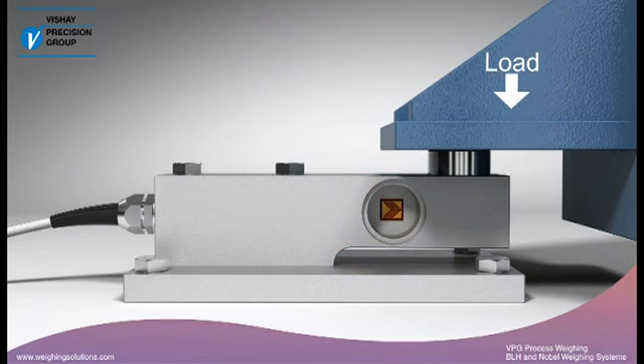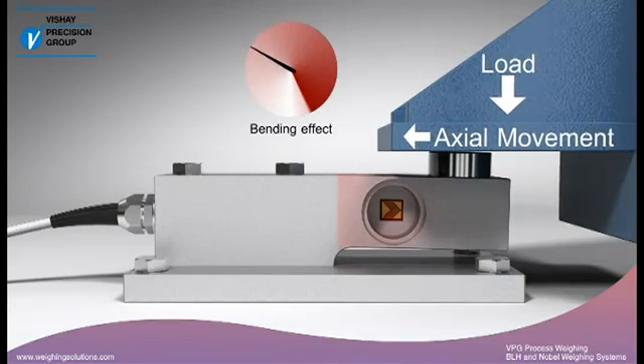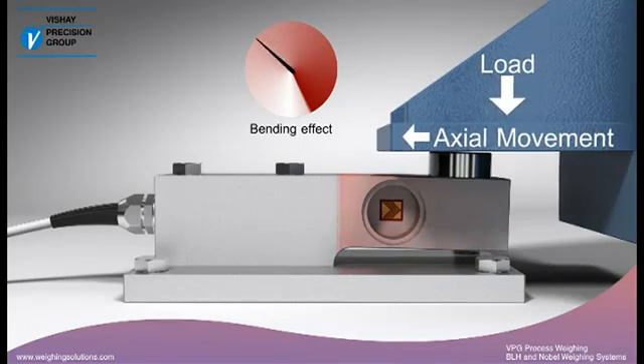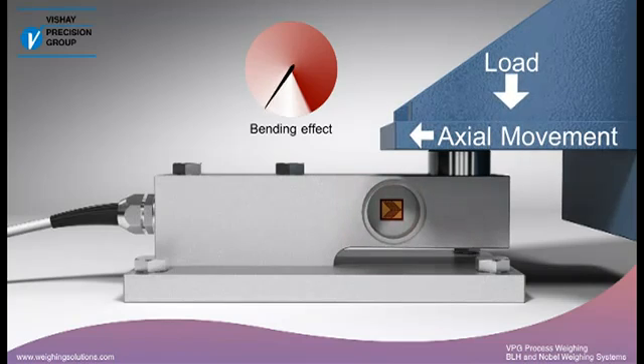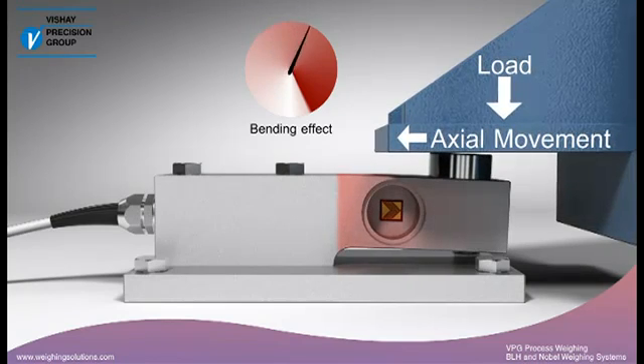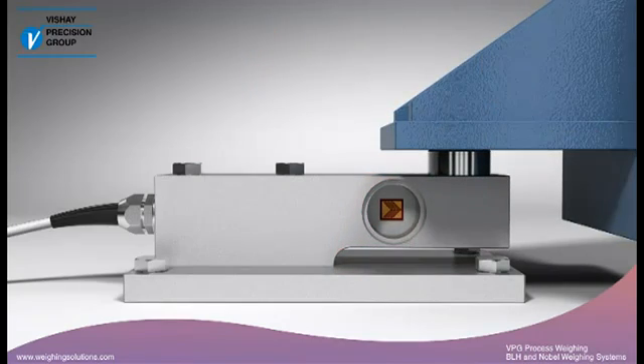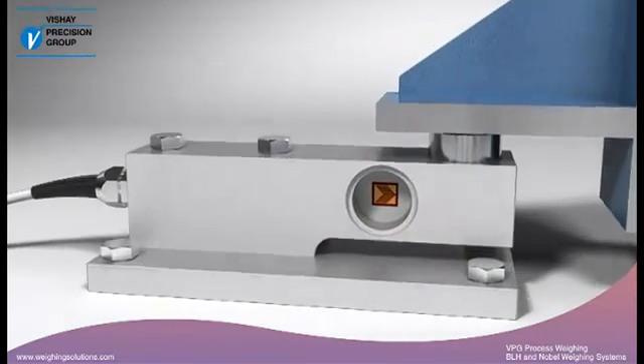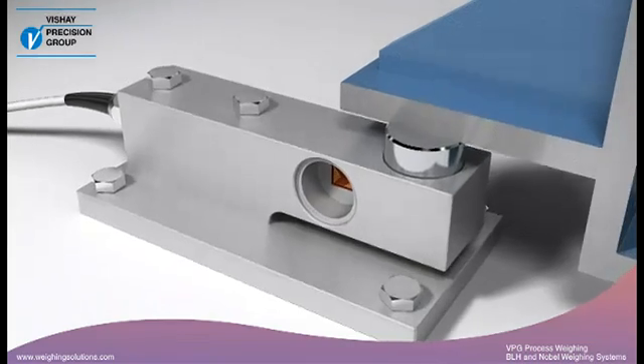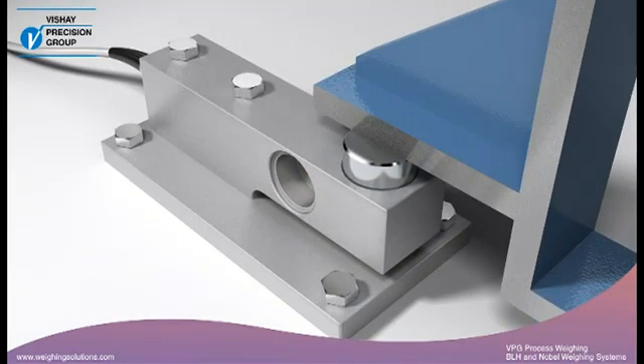In a real process weighing application, however, the bending effects can change unpredictably due to thermal or structural movement. These additional strains result in measurement errors. The side loads can be in any direction, caused by agitation, wind loads, or the flexing of structural supports and piping connections.